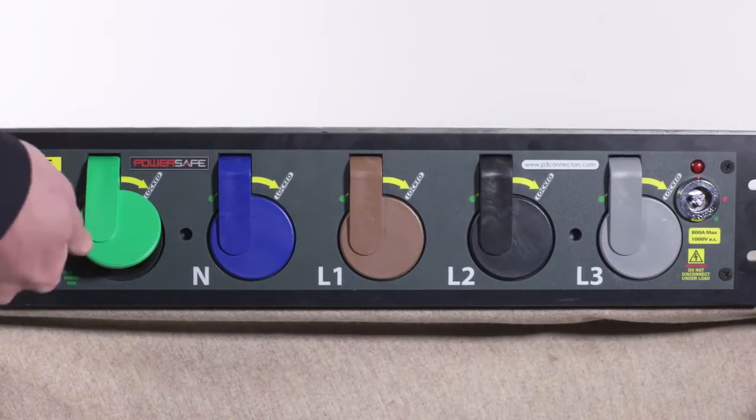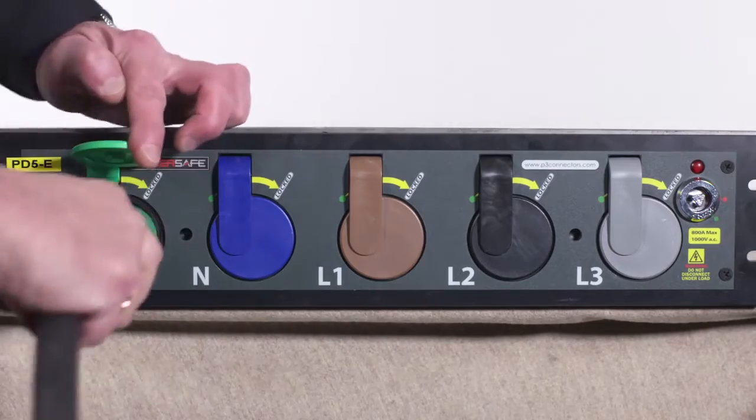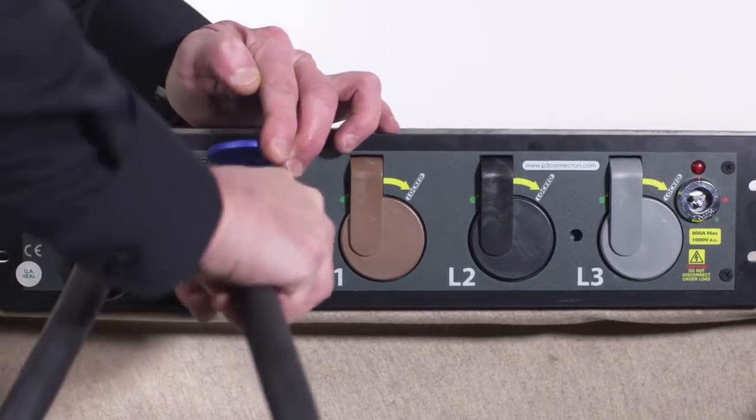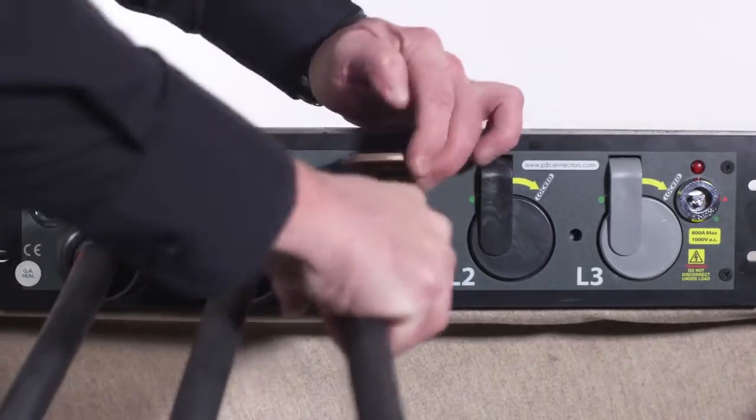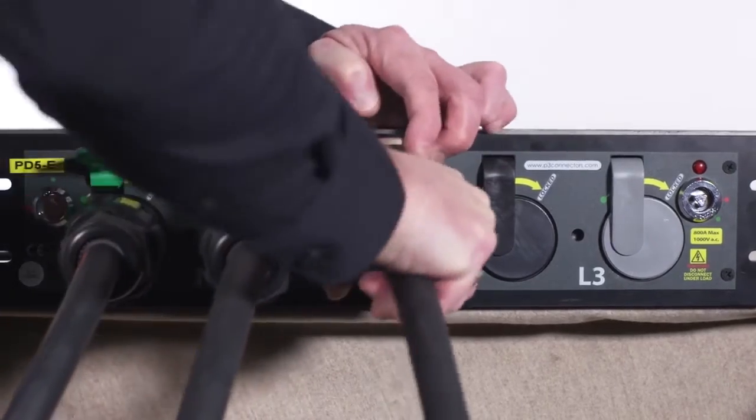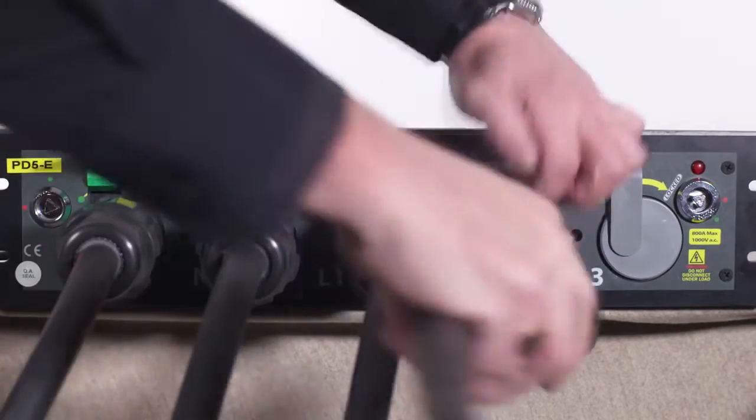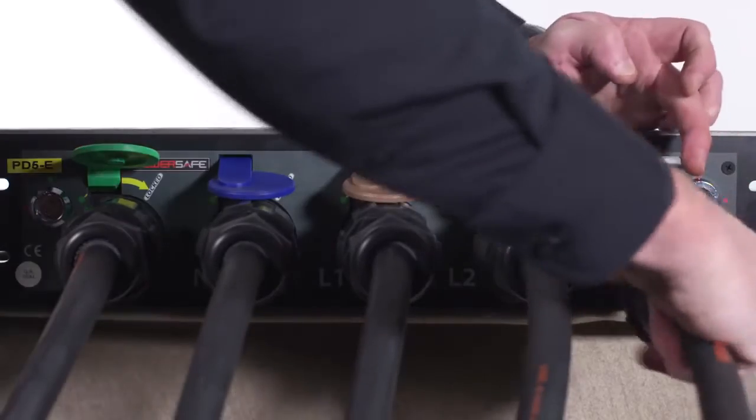PowerSafe connectors can be used with our sequential mating units. These units assist with the safe and controlled connection of the single core power cables by controlling the sequence of connection to ensure earth and neutral connections are made before phase connections can be made, thereby improving safety by eliminating connection errors and ensuring safety circuits are always connected.